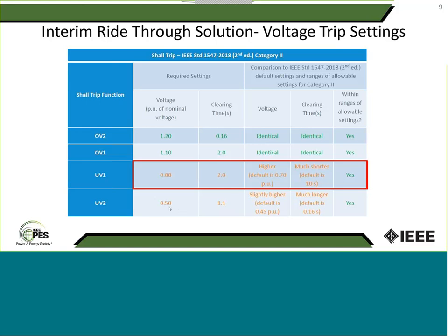The momentary cessation mode really helped us with that discussion, and the reason is, as I said, momentary cessation is the mode in which the generators stop producing current, okay? And most of the faults on a distribution system, if the fault impedance is not too high, will cause the voltage to go below 50%. Again, if the fault impedance is high, then you may not even be able to detect that with your regular overcurrent relays anyway. But most faults will bring the voltage on the distribution wires below 50%.